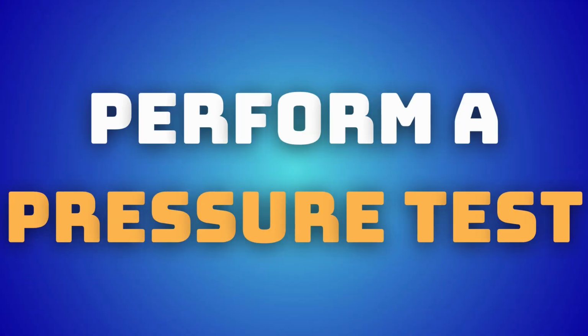Step one of any good vacuum is a proper pressure test. I've done a video on pressure testing and leak searching these systems, I suggest you go check that out. Make sure you've done a good pressure test, passed all the things, haven't skipped any corners. Otherwise, you're wasting your time with the evacuation. You're just going to be chasing your tail, and you're going to end up having to go through all the pressure testing anyway, because the likelihood everything in this system is perfect is slim.